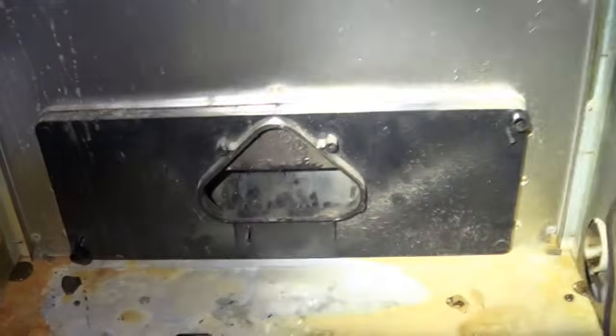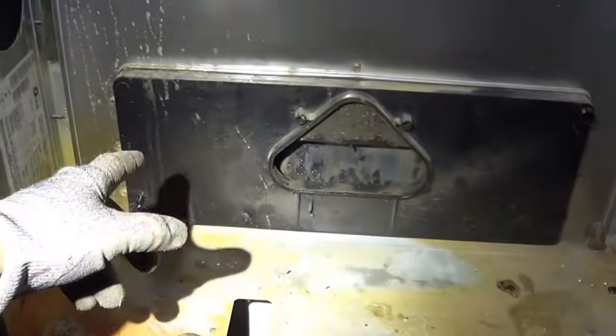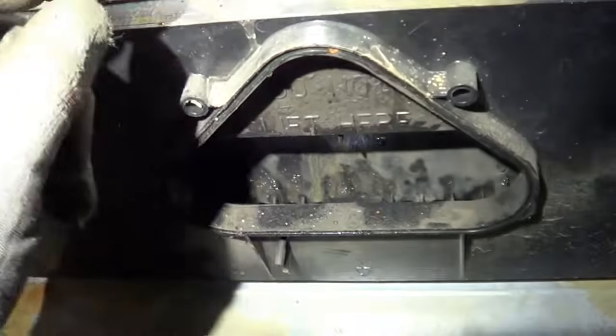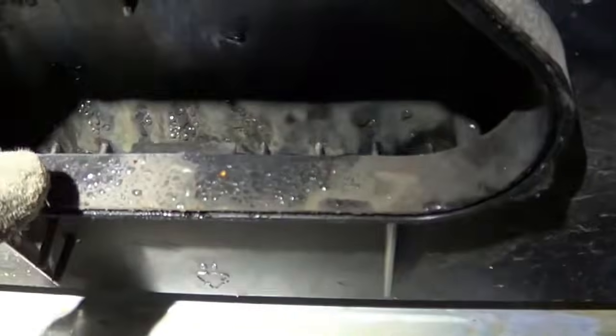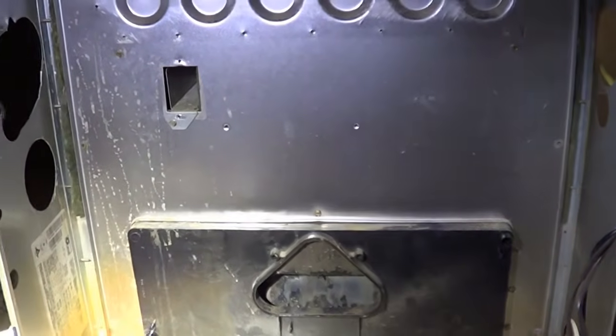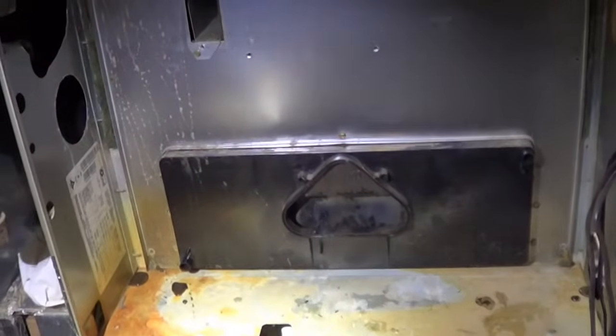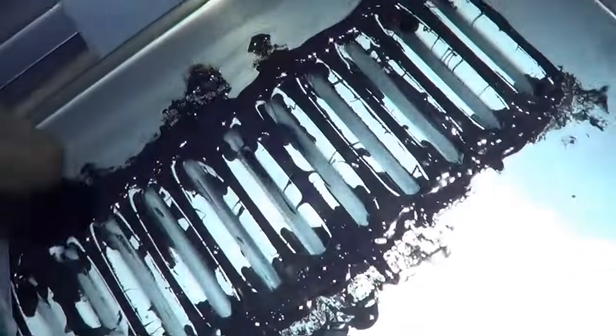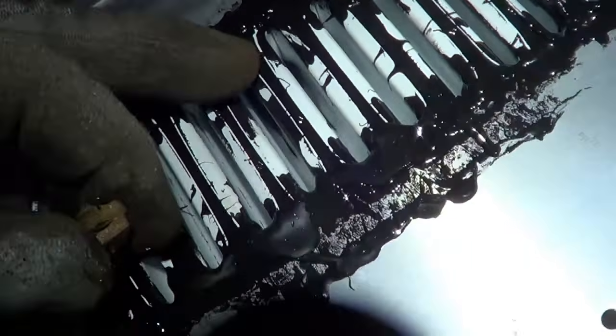Not all secondary heat exchangers can be cleaned. This is a Carrier. They actually did a bulletin on these so the secondary is under warranty, but it's clogged up, and the way it's constructed, it's factory welded plastic, and it doesn't have the turbulators. So in this one you just have to change the furnace or change the heat exchanger itself. But I'll pull it apart and I'll show you what it looks like on the inside. On this Carrier secondary heat exchanger, here's a clean one. Now it is magnetic, but it's somewhat stainless. You can still have stainless that's magnetic. And then here's the clogged one.